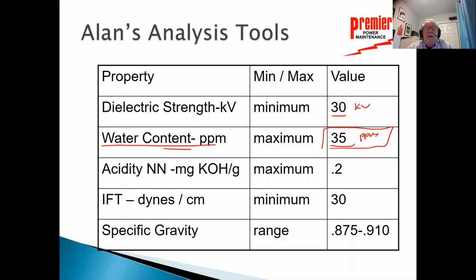So if I take a cold sample, I may come back with an oil sample where it says the water content is 15 or 20 parts per million, which is a good number. But if I don't take into account the temperature I'm dealing with, that could still be a bad number. There's just not room in the oil for any more water.